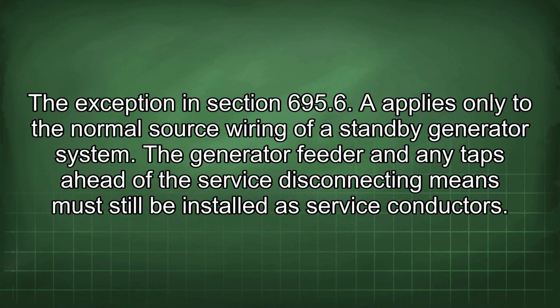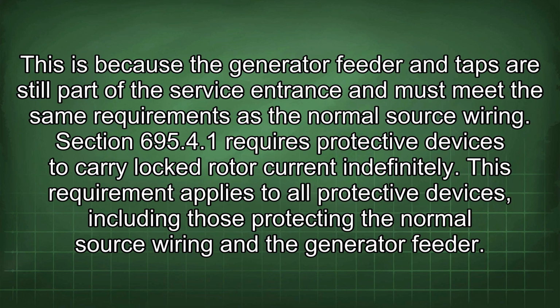The exception in section 695.6 applies only to the normal source wiring of a standby generator system. The generator feeder and any taps ahead of the service disconnecting means must still be installed as service conductors. This is because the generator feeder and taps are still part of the service entrance and must meet the same requirements as the normal source wiring.